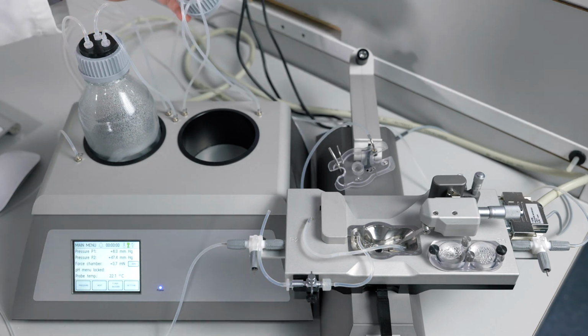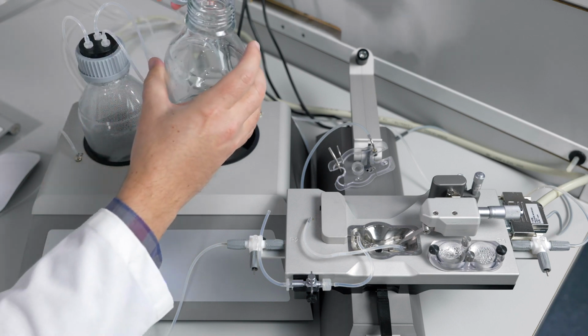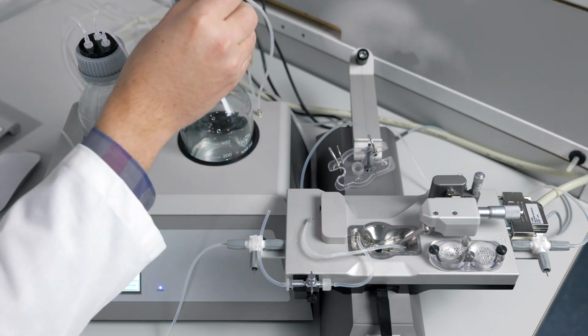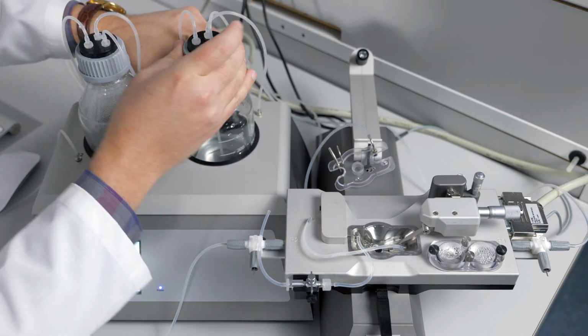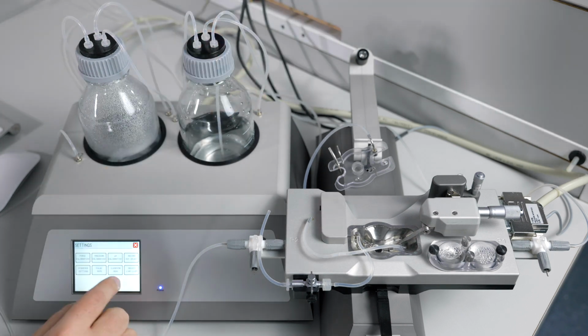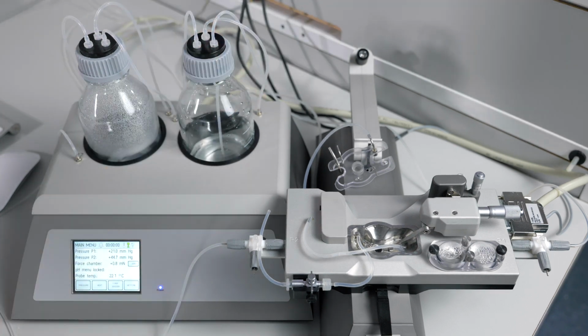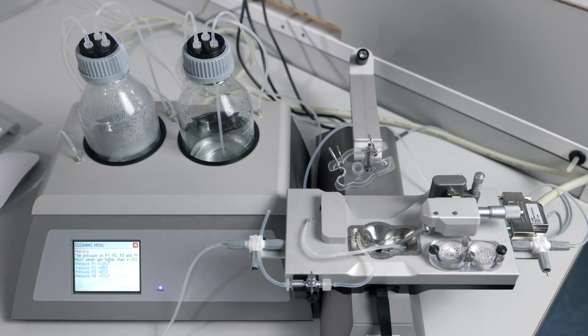We will now repeat the process we did with air with the distilled water. Tighten the cap on P1, enter the cleaning menu, and turn on pressure. Once you can see water dripping into the P2 waste bottle, you know that all of your lines are filled with distilled water. You will let this continue to run.